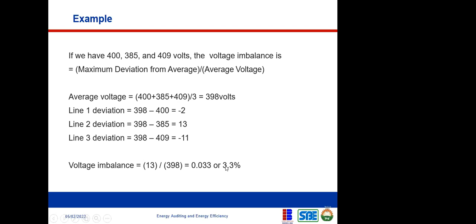Here's another example. The average voltage between these three phases - 400, 385, and 409 - we divide by 3 to get the average voltage, and we calculate the voltage deviation from each one. We have the first as -2, then 13, and -11. So 13 is the highest. We divide 13 by the average voltage and get 3.3. So this is how to calculate your voltage imbalance.